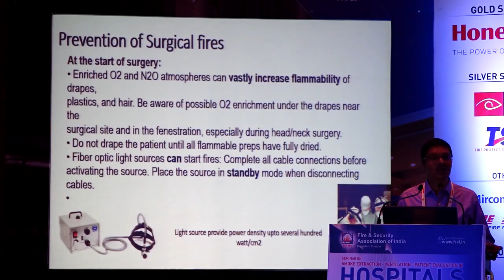The biggest challenge is with the electrosurgical system, the cautery machine, which you use for cutting and coagulation. You are actually using RF current, and if it is not properly taken care of, it may lead to an issue. More than that, the biggest challenge is to convince the surgeons: this may lead to a problem, so please take some measures. We have some cases where there are burns, but the surgeons refuse to change their practice. This is one problem which we face, but we have to handle it tactically so that they will not make the mistake.